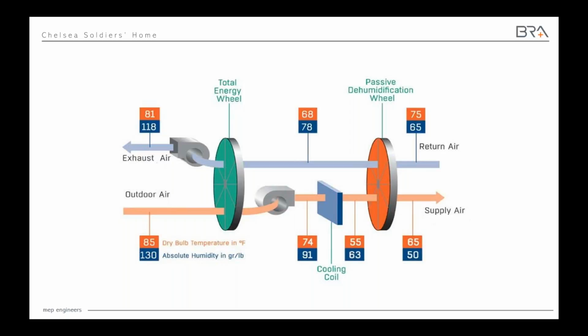Now I keep mentioning the 500-pound gorilla for load reduction is the ventilation air in these types of high intensity buildings. So we have to really maximize our heat recovery from our exhaust air and capture that heat and put it back into the supply side. So this is a diagram here of our air handler.